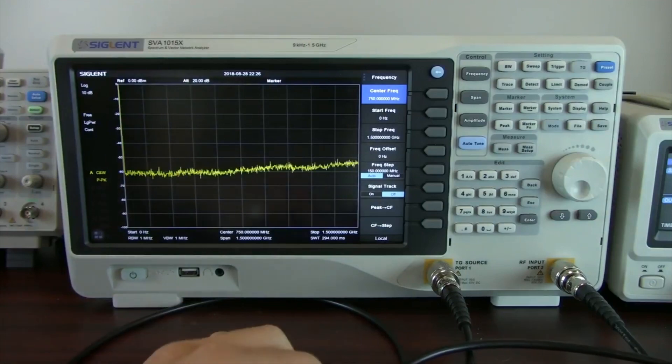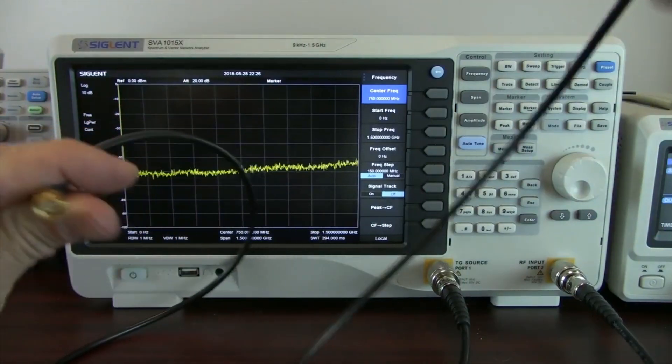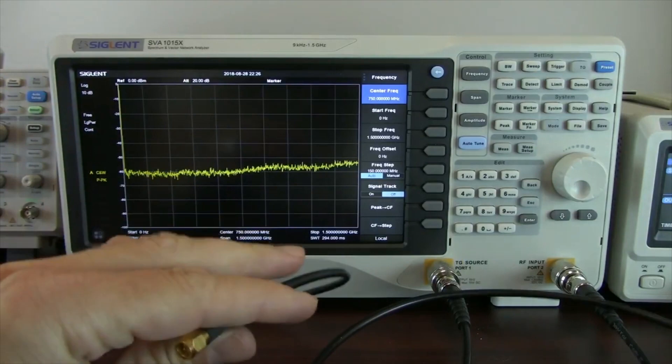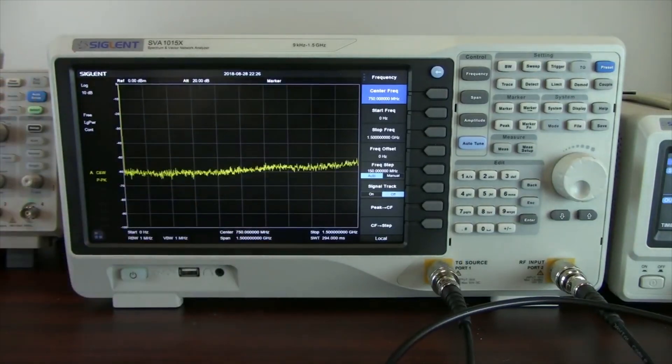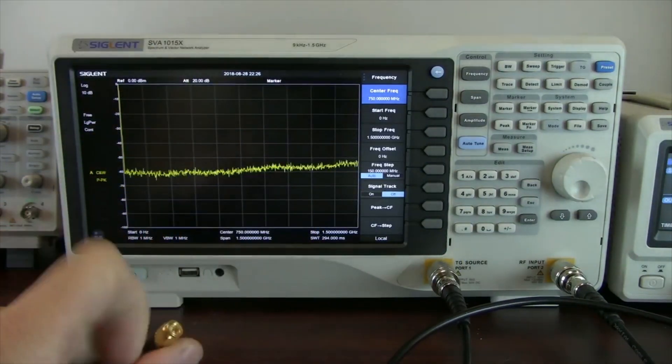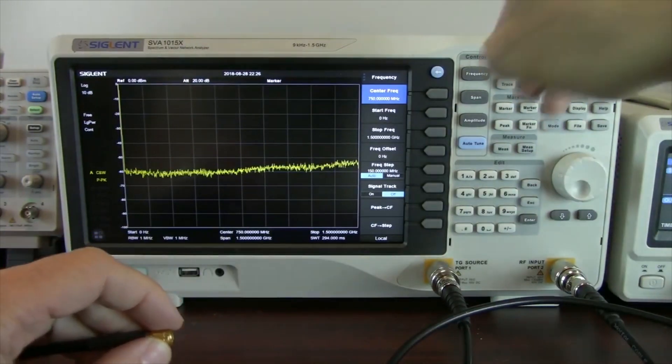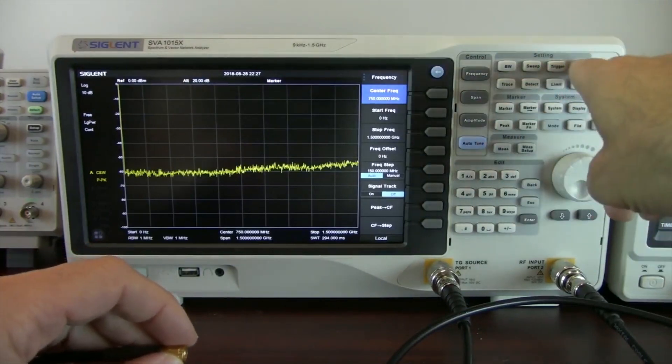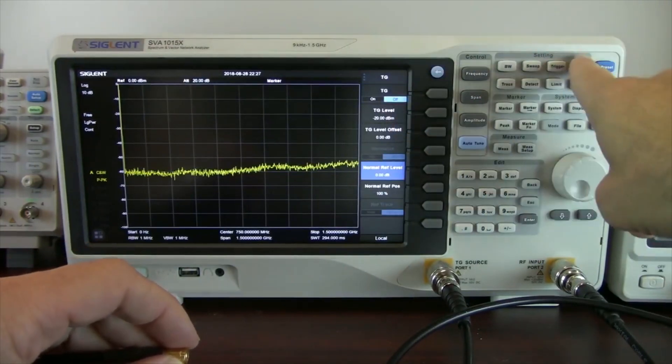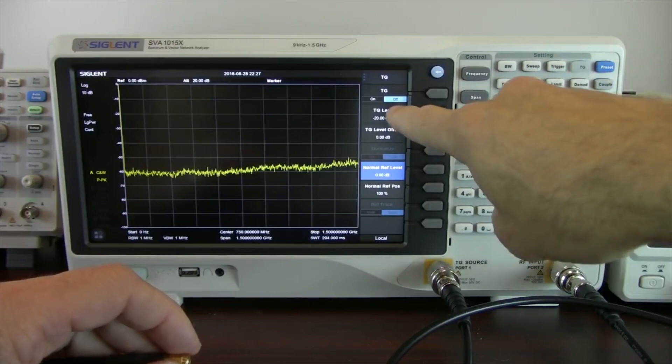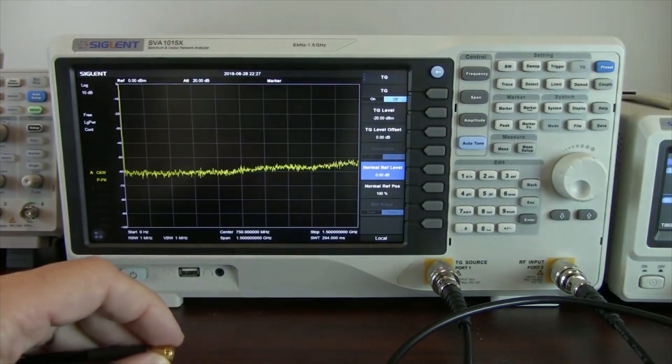So the first thing we're going to do is get rid of the errors involved with the cabling before we connect anything up. We have our tracking generator source, and we're actually going to be knocking down the signal a little bit. The spectrum analyzer tracking generator can go to minus 20 dBm.